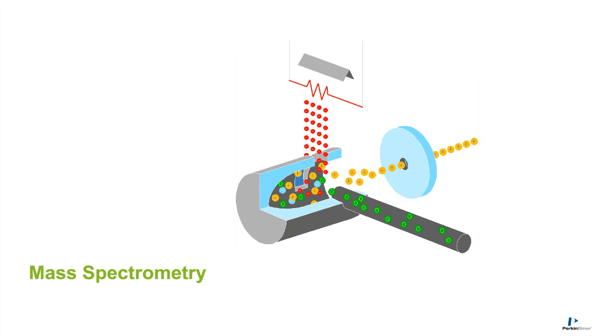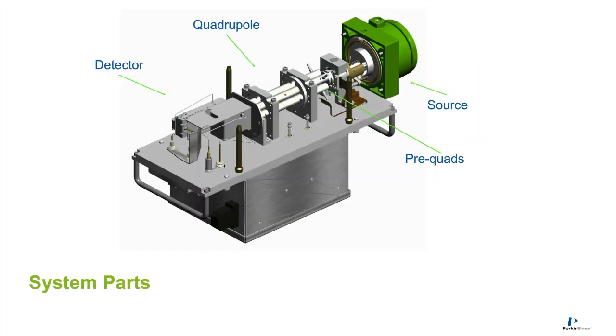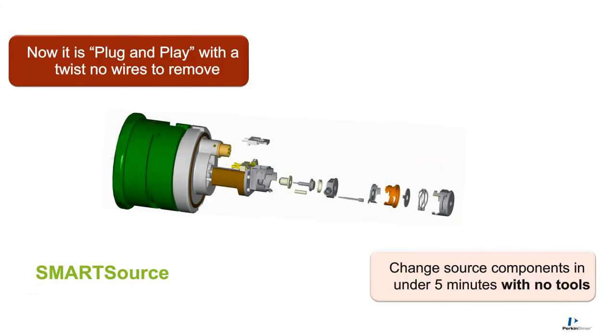Okay, very good. So let's move on to some mass spec maintenance and troubleshooting. So here we have the system parts. We have pre-filters on our rod set so that the analytical rod set does not get contaminated. Our source is plug and play. It takes less than 2 minutes to put this together, and another 2 minutes to take it apart. All these individual pieces can be purchased.